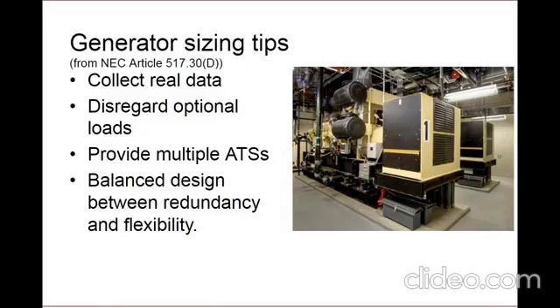Disregard some of those optional loads that you have connected to the system, such as chillers, when you're calculating that generator size, and you can do that on the basis that this equipment will only be connected when load is available, because it is optional. You can provide multiple transfer switches that allow you to step load the system, thereby keeping the generator size at bay. And of course, don't forget, there's always that careful balance between oversizing a generator and the need for redundancy and reliability.